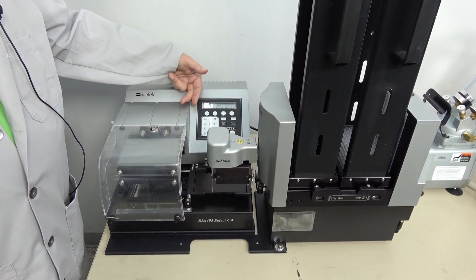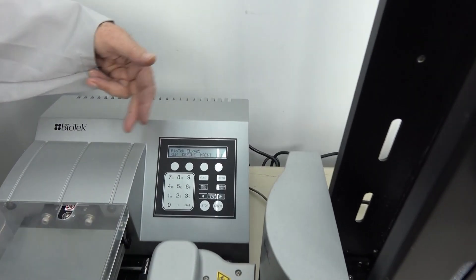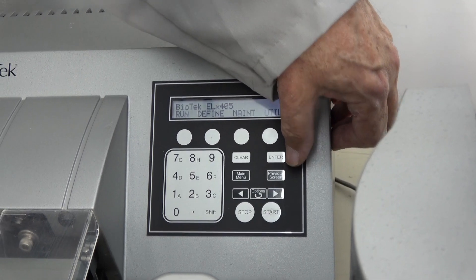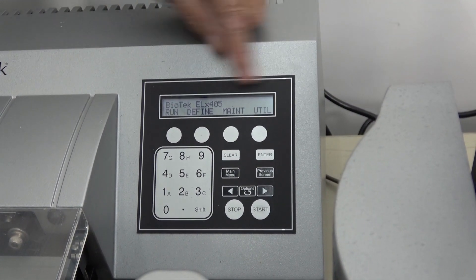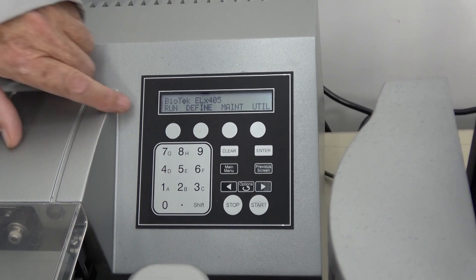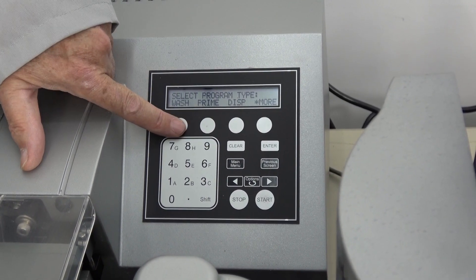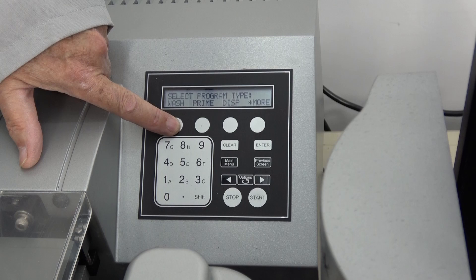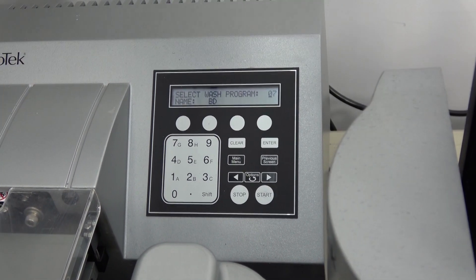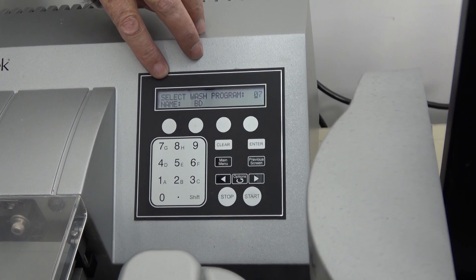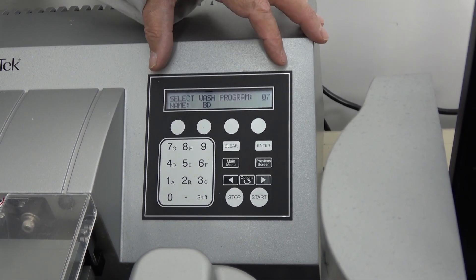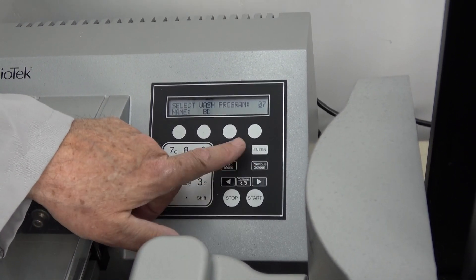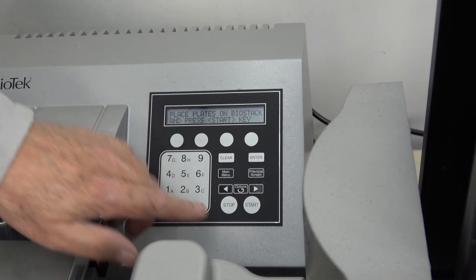As I said, fairly simple menu. Not a lot of buttons, but there's plenty of them to get along. Your main menu, previous screen. If you get into an area you don't want to be in, just use the previous screen. The main menu, which is here. In this case, let's say we want to run one of our wash protocols, and you can create your own protocols. This is one that is going to use plate well B. You've got some large naming conventions. Anyway, that's the one we're going to use. We're going to just press enter. It tells us what to do to start. Press start.